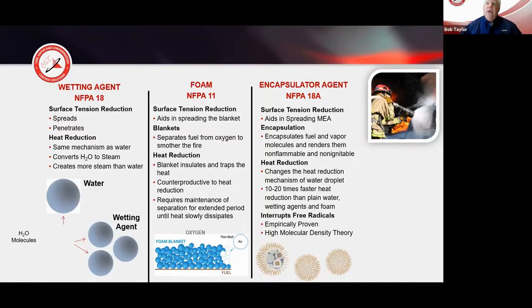Then we deal with foam. Foam flows across the surface of a liquid, or sometimes Class A materials, forming a blanket. The quality of the blanket means everything because it separates the fuel from the oxygen to smother the fire. But if that blanket gets interrupted or pulled off, all the conditions are back on the table for the fire to worsen.